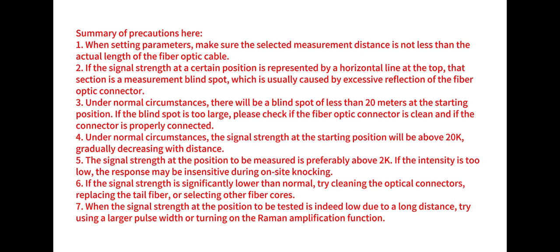If the blind spot is too large, please check if the fiber optic connector is clean and if the connector is properly connected. 4. Under normal circumstances, the signal strength at the starting position will be above 20K, gradually decreasing with distance. 5. The signal strength at the position to be measured is preferably above 2K. If the intensity is too low, the response may be insensitive during on-site knocking.